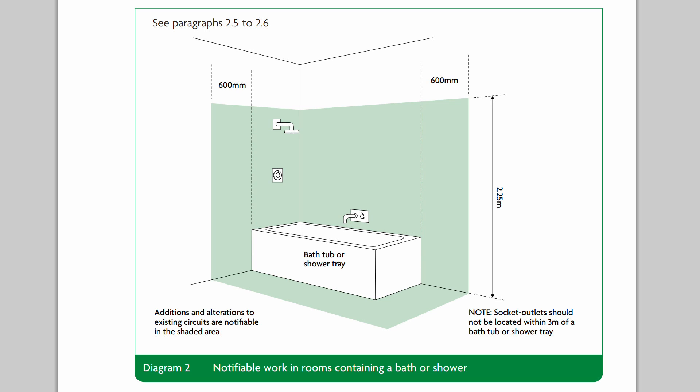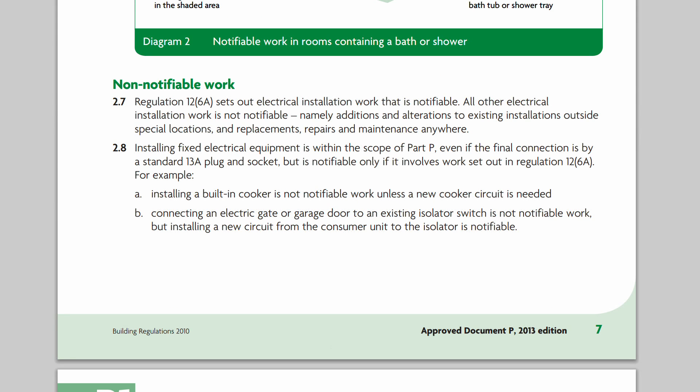The special location zone extends 600mm from the bath or shower tray in all directions and up to a height of 2.25m from floor level. Anything in that area is considered notifiable work. There is also a note from BS 7671 that socket outlets should not be located within 3 metres of it. In a typical bathroom, only a few things will be within that zone — electric showers being the prime example, possibly an extractor fan. Everything else, such as lighting and towel rails, is not notifiable.